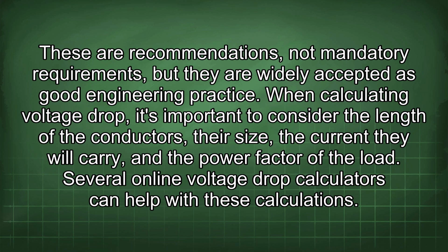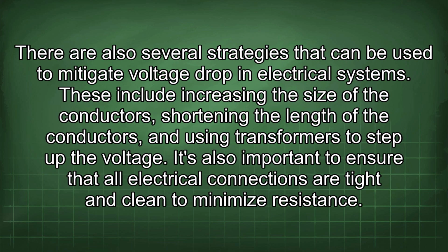When calculating voltage drop, it's important to consider the length of the conductors, their size, the current they will carry, and the power factor of the load. Several online voltage drop calculators can help with these calculations. There are also several strategies that can be used to mitigate voltage drop in electrical systems. These include increasing the size of the conductors, shortening the length of the conductors, and using transformers to step up the voltage. It's also important to ensure that all electrical connections are tight and clean to minimize resistance.